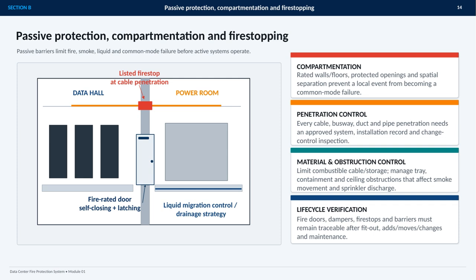Liquid migration needs a defined control and drainage approach, while combustible cable and storage materials should be limited. Tray, containment, and ceiling obstructions must be managed so they do not interfere with smoke movement or sprinkler discharge. Finally, this protection has to remain effective throughout the facility's life. Fire doors, dampers, fire stops, and barriers need to stay traceable after fit-out, additions, moves, changes, and maintenance.